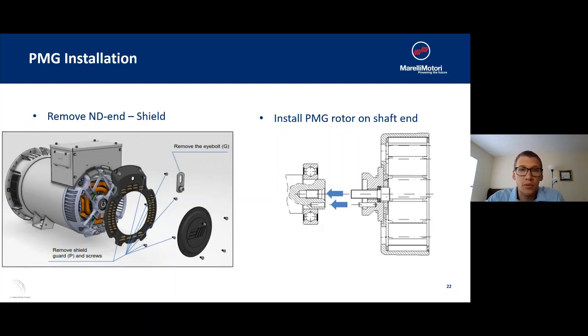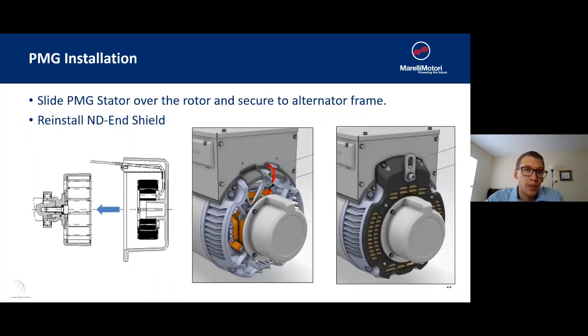From that point, after we've installed the PMG rotor, we're going to slide the PMG stator over the rotor and secure it to the alternator frame. From this point, we're going to run the wires from the PMG into the terminal box where we're going to connect them to the AVR, and then we just have to reinstall the non-drive-end shield of the generator just to clean it up a little bit.